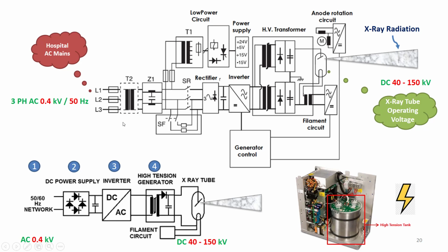To solve this problem, currently we use a high-frequency X-ray generator like the one in this slide. So how does a high-frequency generator work? In order to reduce the size of the high-voltage transformer, we need to increase the operating frequency of the AC source. So this is the solution for the above problem. Increasing the frequency of the source will minimize the size of the transformer. In Lebanon, we use a 50 Hertz AC source. So in order to solve this problem, we use inverters, which are DC to AC converters with an operating frequency between 20 kilohertz up to 300 kilohertz depending on the manufacturer.